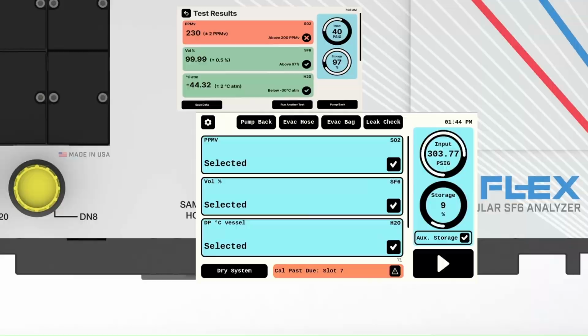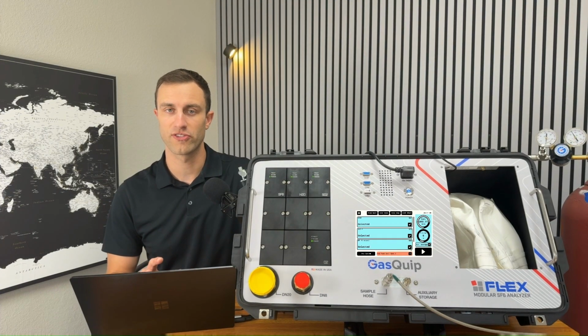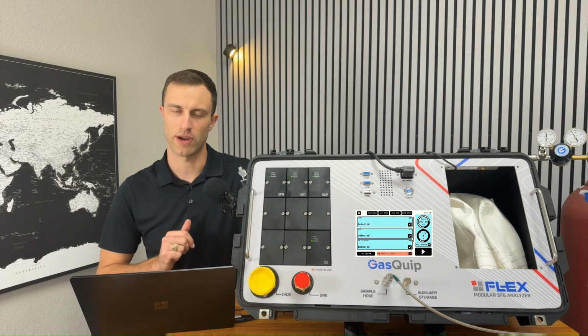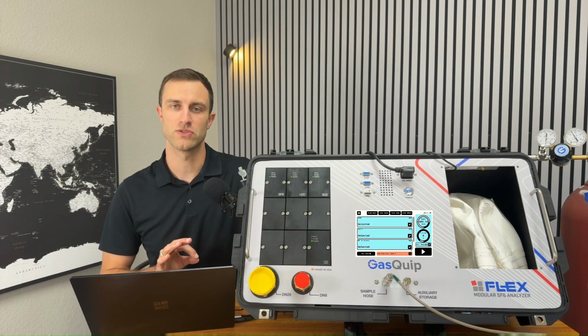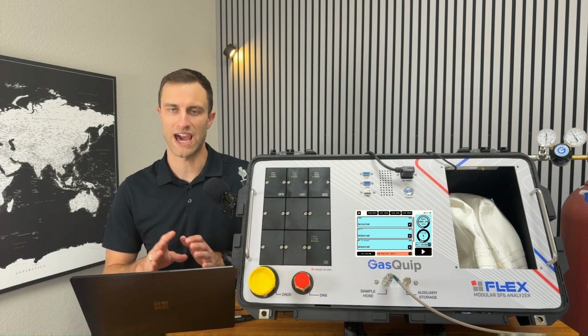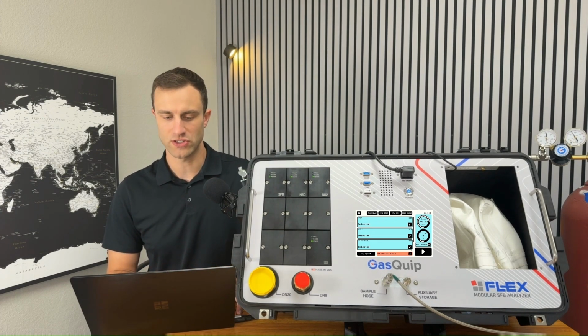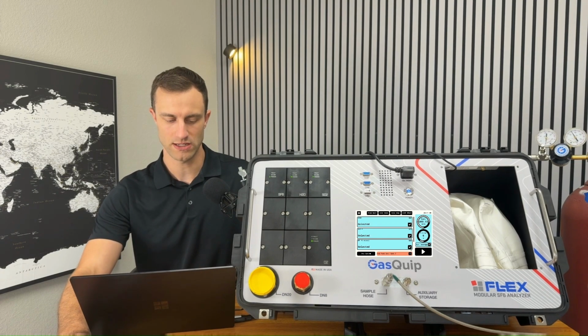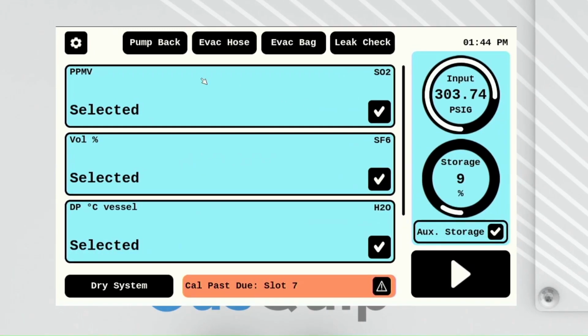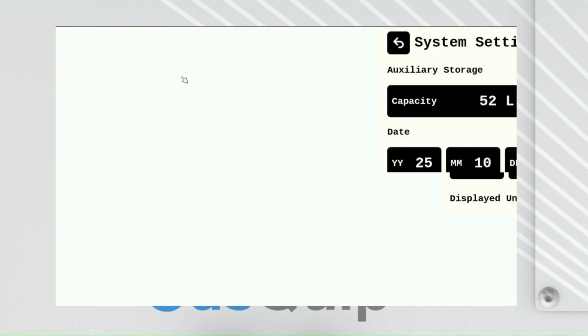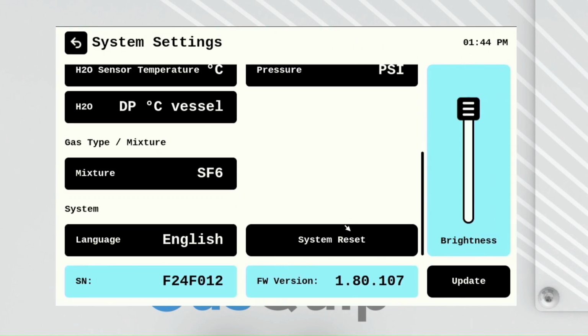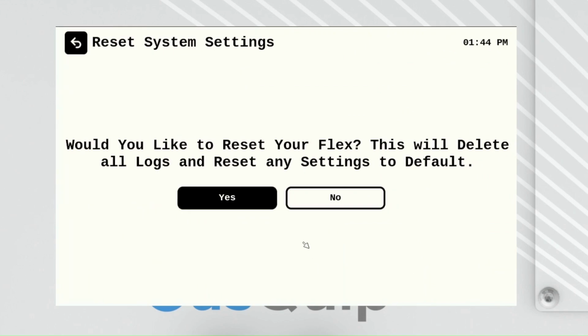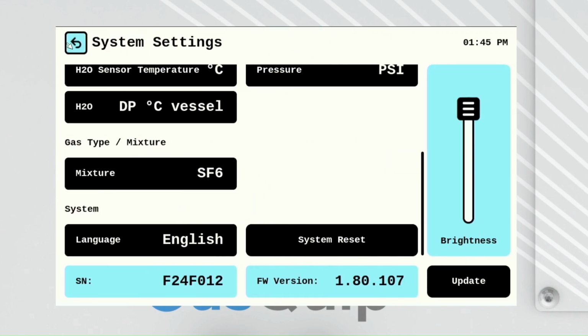The first thing that I would do is turn your analyzer on and off, wait about 5 to 10 seconds, and then turn it back on. If you don't see those issues anymore, then you might have cleared the cache of the system and it might be fine. If that doesn't work, you can also run a system reset. So if we go back to the close-up here, we'll go to System Settings and then go to System Reset. What that's going to do is delete all the logs and reset all the settings to default, and also clear the back-end cache of the system to help eliminate some of the issues that you might be seeing.